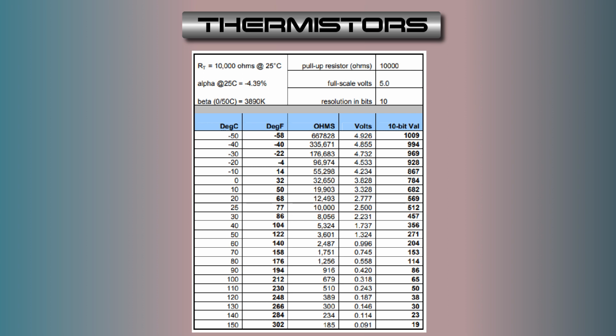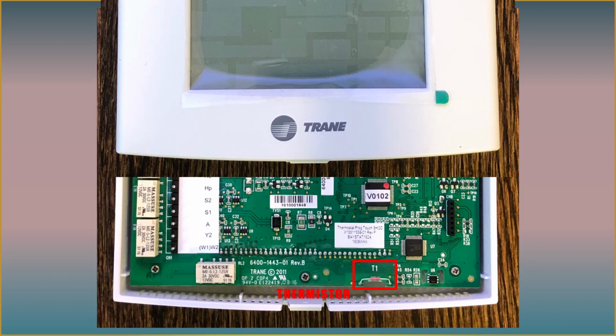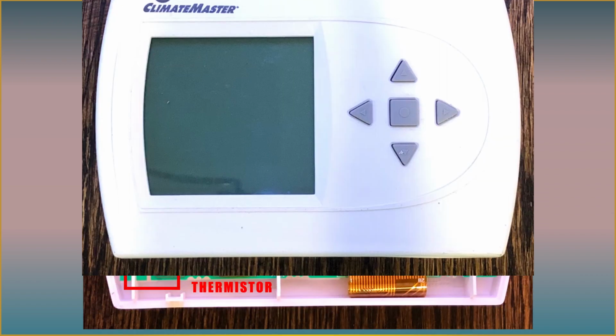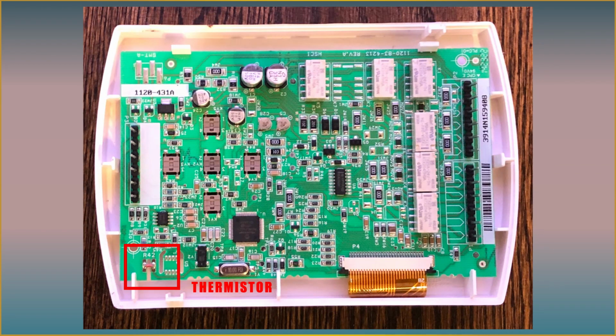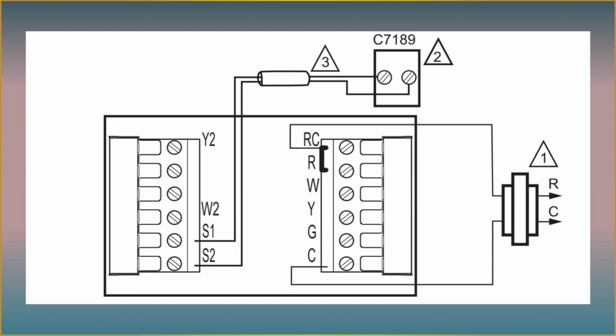So by using your multimeter, you can measure the resistance of the thermistor or sensor and compare it to a chart and see what the temperature is reporting. All modern thermostats use onboard thermistors as the temperature measuring device. So how does the thermostat function with the remote sensor? It accomplishes this by sending out a DC voltage from one of the remote sensor terminals, S1, down the wire and to the thermistor. It changes the resistance of the thermistor, lowering the DC voltage output to a lower voltage, which is based on the space temperature. It then travels back through the wire to the other remote sensor terminal, S2. The temperature could then be interpreted as the temperature of the space.